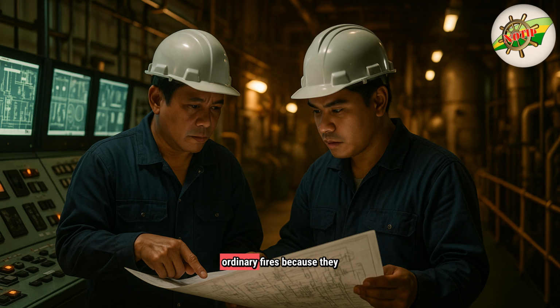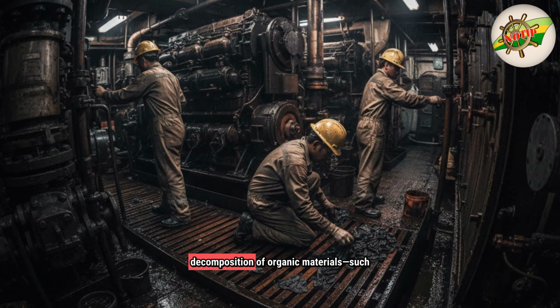Process hazards differ from ordinary fires because they originate from internal chemical or thermal changes within machinery, fuels, and structural materials. Let us examine each major hazard, beginning with dry distillation. Dry distillation is the decomposition of organic materials such as wood, oily rags, paint residues, insulation, or cargo when exposed to high heat in the absence of sufficient oxygen. As temperature rises, the material releases flammable vapors. These vapors accumulate unseen, and when oxygen becomes available, they may ignite violently.